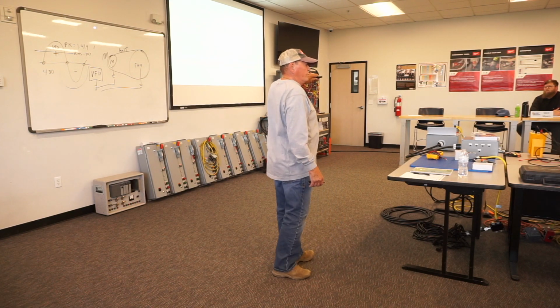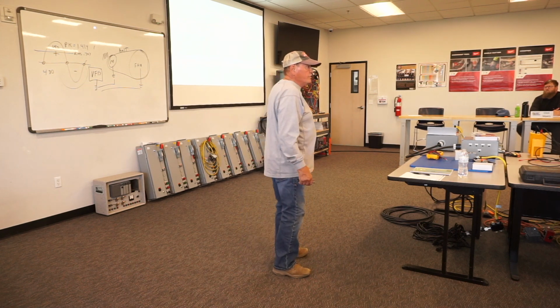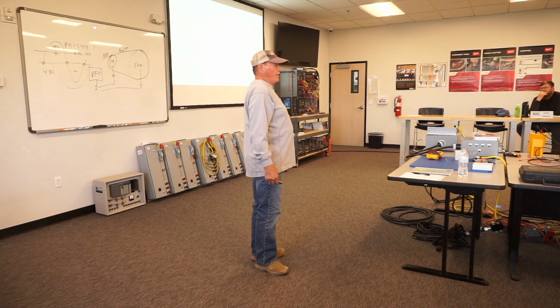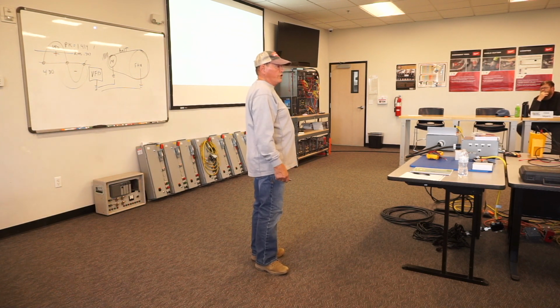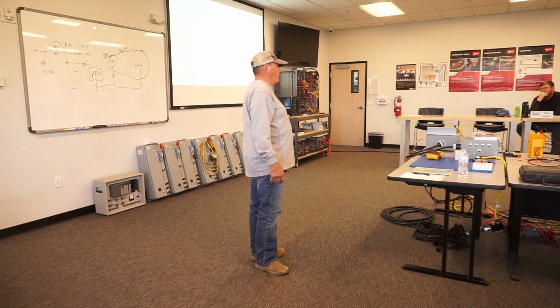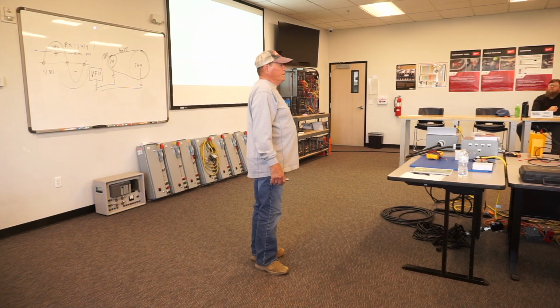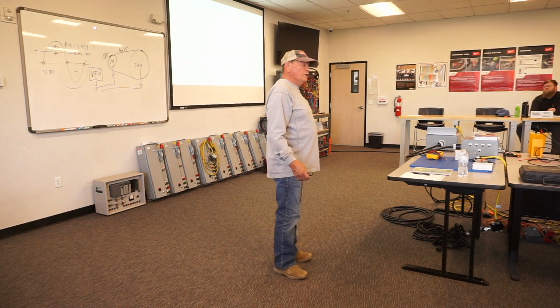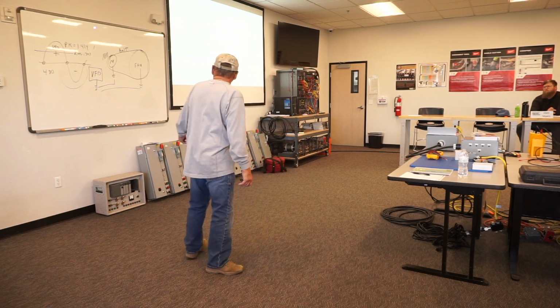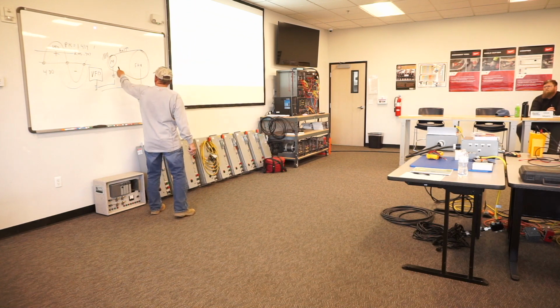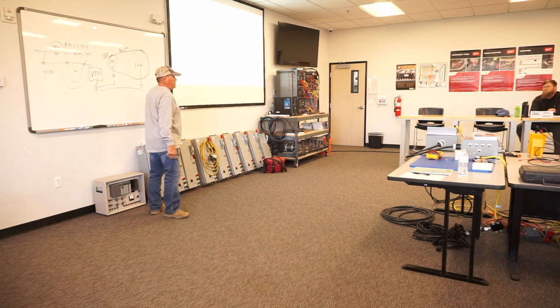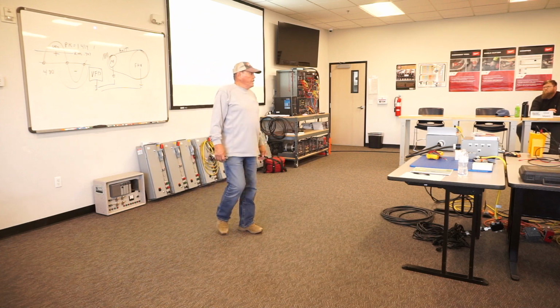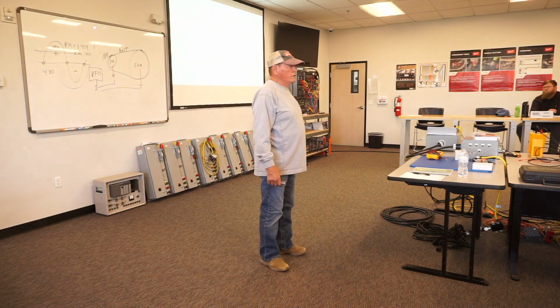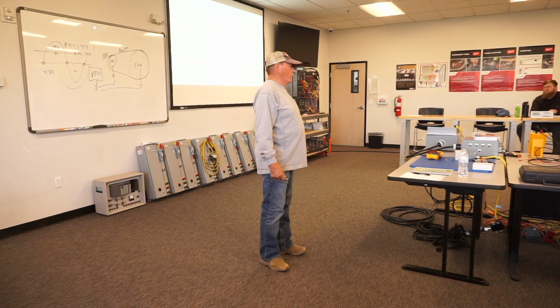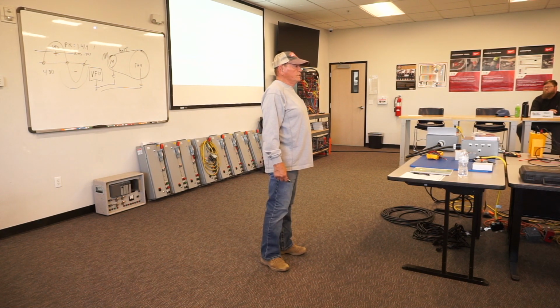The shaft is attached to some grounded means, because my motor's not bonded, my motor's simply grounded so I don't get shocked. So it's a high impedance path for high frequency. Building grounds are a high impedance path; to high frequency, it's an open circuit. So my metal parts are a much lower impedance path back to the drive than the NEC ground that grounds the motor, because the motor is grounded for personal protection, not for high frequency.